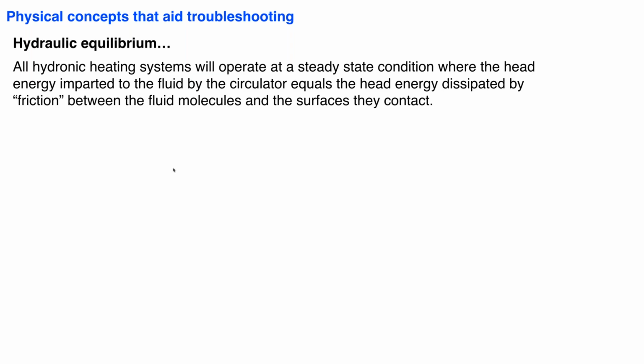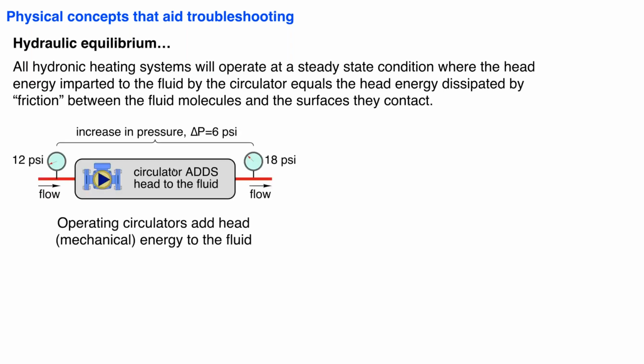It's just like slowing your car down with brakes. Your brakes ultimately convert the kinetic mechanical energy of the car into thermal energy. So again, hydronic systems seek this balance. So circulators add head energy to the fluid. And the evidence that that energy has been added is an increase in pressure. So for example, here we're going in at 12 PSI. We've got an operating circulator. We're injecting this head energy to the fluid, and we're coming out at 18 PSI. We could actually calculate how much head energy in feet of head based on the change in differential pressure, okay?